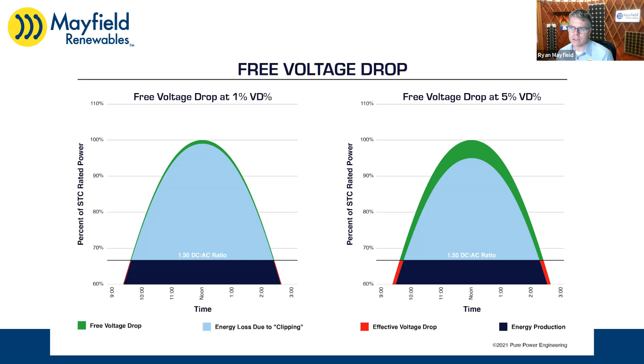We had done a paper a while ago on voltage drop specifically, not getting into free voltage drop, but essentially there's the voltage drop you have, and what we're really concerned about, what you're showing here, is the energy production—that's ultimately what we're getting paid for, the kilowatt hours. So you want to take that voltage drop and translate it into what it does to your energy production over the life of the system, and quantify that. So in short, you do your math, figure out what it is, and then you have to do the modeling to figure out what the real effective loss is.